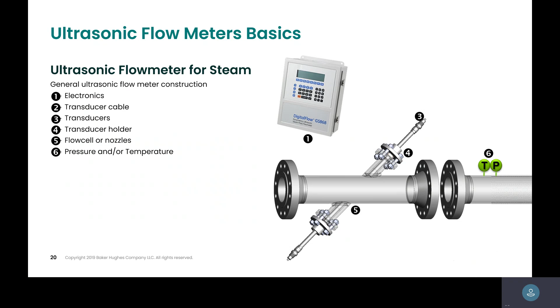If you need mass flow, you need to take in temperature and pressure, because ultrasonics is usually a velocity measurement - with the ID of the pipe, you get volumetric flow. If you want mass flow, you need that temperature and pressure.